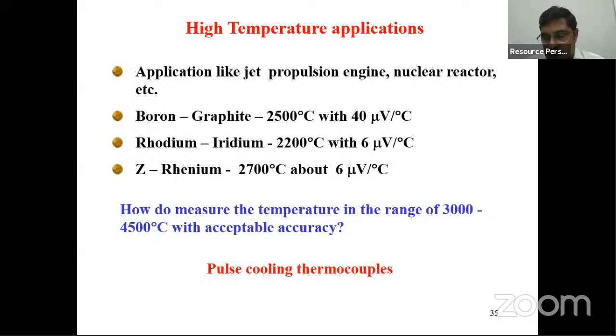Let's see how it can be done. Basically, you can take either a K-type or an R-type thermocouple and keep it in a small enclosure. Normally this thermocouple is cooled by supplying normal air. Whenever you need the temperature measurement, you close the normal cooling air and supply the hot gas, which may be above 2000 or 3000 degrees Celsius, for only a few seconds. Within those few seconds, you measure the thermocouple response, that is, the increase in temperature of the thermocouple. Then you shut off the flow.